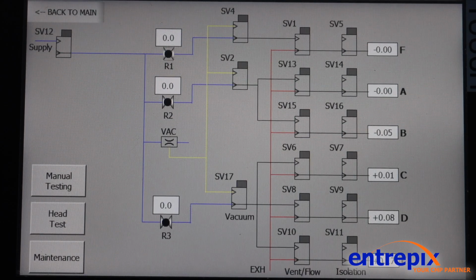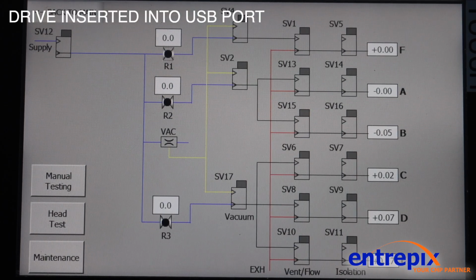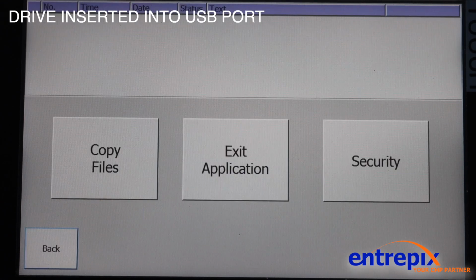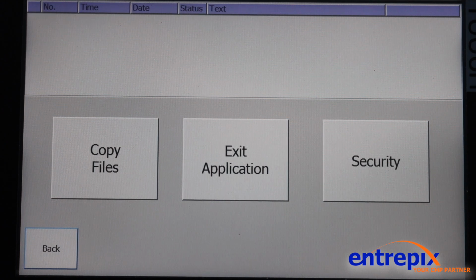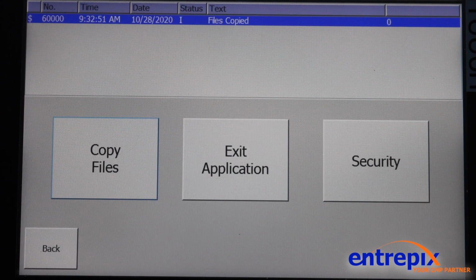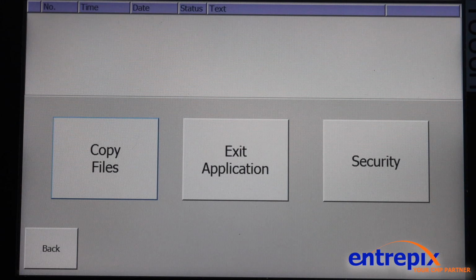You can now collect the test results using the USB port. From the main service screen, select Maintenance. From here, select Copy Files. The tester retains all data indefinitely, so you can go back at any time to recollect this or any other head results. Once you've selected Copy Files, it will copy the data onto the USB drive or send it out and make it available on the Ethernet port located at the rear of the tool.